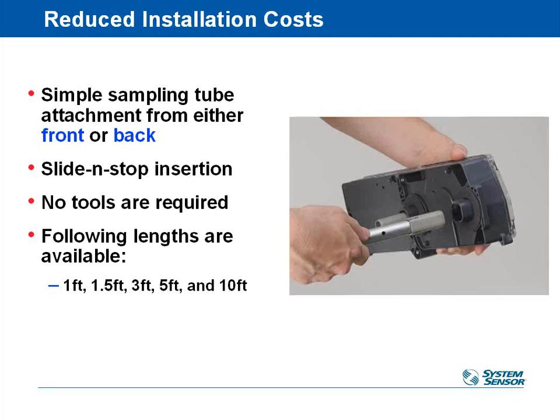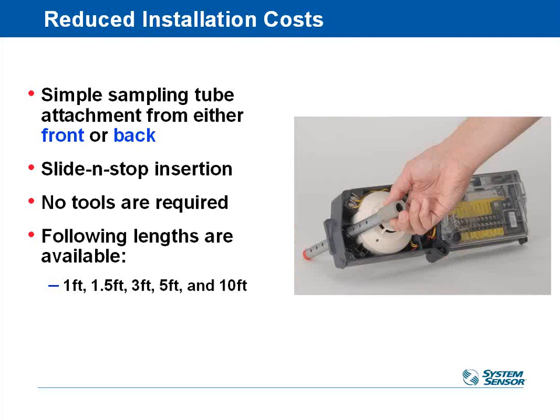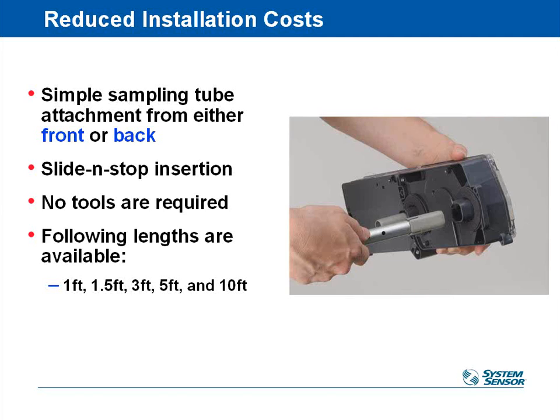This shows the back side here. So like I said, you can install the tube from the front of the detector if the detector is already mounted on the duct, or you can install it from the back of the detector and then put the detector through the duct. You can also see here the front one here is the sampling tube. That's the long tube from 1 to 10 feet long with the sampling holes on it. The one in the middle of the detector is the discharge tube. That comes with the detector. It's like a 3-inch tube. It fits on there. The sampling tube you order separate because we don't know what length you need. The discharge tube is always 3 inches, and it comes with it. So the air comes in these holes in the front of the sampling tube, makes its way through the head of the detector, goes through, and then comes out the discharge tube back into the supply duct.